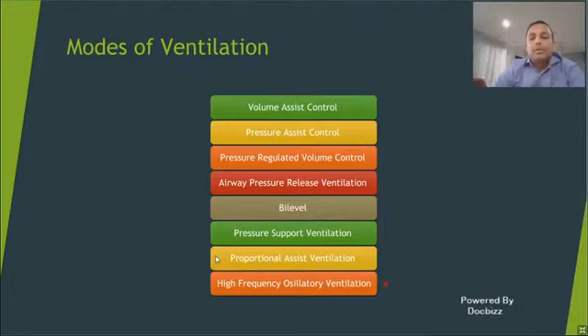So again, most of the modes in the ventilator are divided between either volume control or pressure control. So at any point of time, or at any point of lung compliance, either we can control the volume or we can control the pressure. Once you control the volume, meaning if you want to give a fixed delivered amount of volume, you cannot control the pressure. If the lung is a stiff lung, for the same amount of volume, the pressures go up very, very high. And if the lung is a compliant lung, then for the same amount of volume, the pressures might not go up so high.